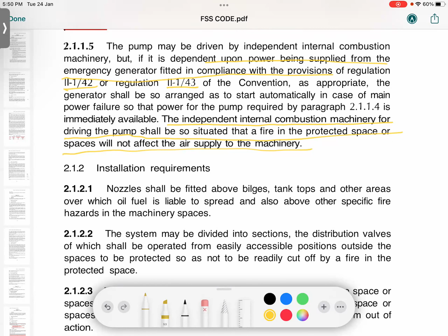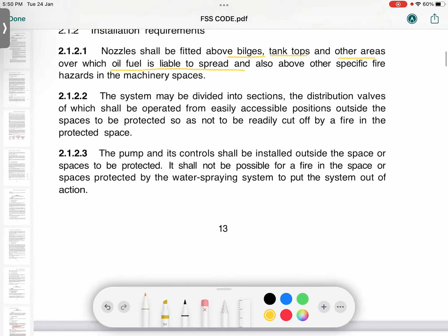So, if your pump is driven by an internal combustion machinery, means an engine driven pump, then it should be located in the fire protected space, means outside of the machinery space. But generally the pump may be driven by electrical power, then it should be coming from the emergency generator. Now the nozzles are generally fitted above the bilges, tank tops, and other areas where the fuel is liable to spread, wherever your fuel can come, right?